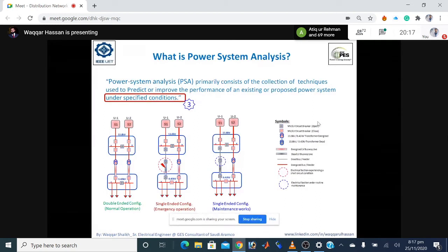A same electrical network can be operated in three different operating scenarios. In the first scenario, there is a double-ended configuration. The power supply normally comes into the transformers, feeding separate sections of the low voltage distribution board. This is a normal operation scenario. Our system may be able to withstand this, and our system demand can be easily fulfilled. So we execute a simulation considering this normal scenario.